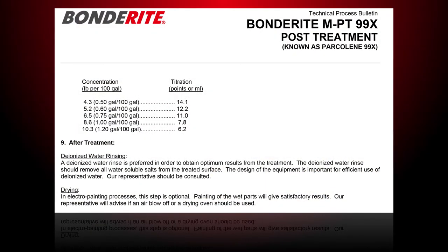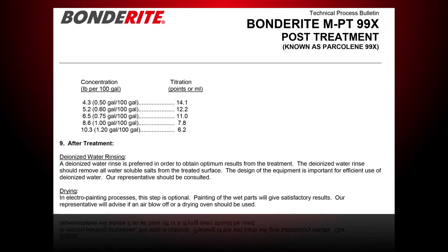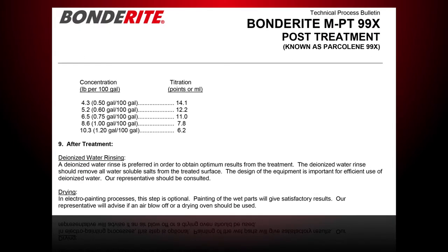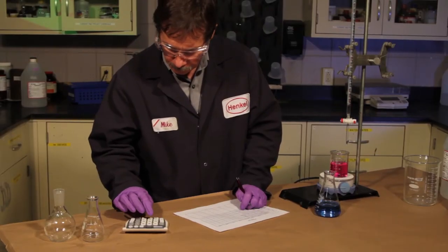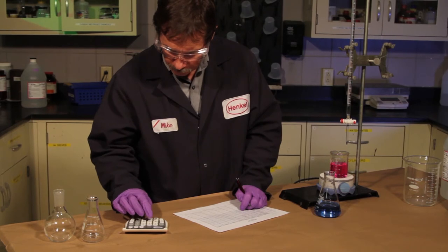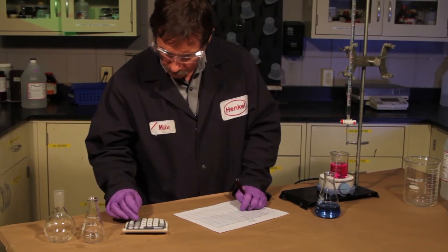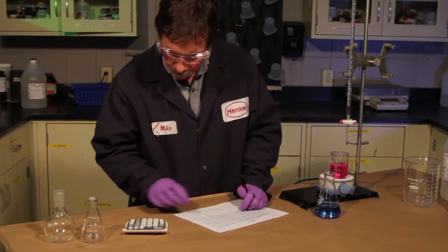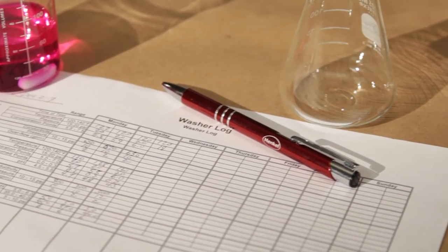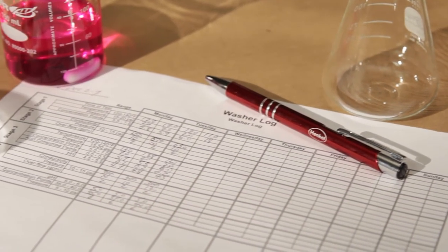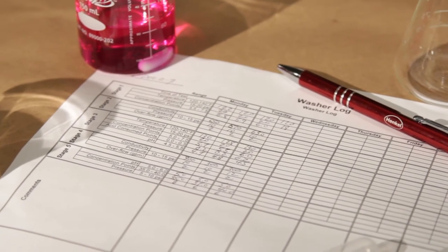The Henkel product data sheet will specify how many points or milliliters of solution to use to control your process. Now that you have measured the number of milliliters, you can compare that with your process control points and use the calculation or chart provided to determine if it is in specification or requires additions or adjustment. Record your values in a log sheet or other quality records and make note of any additions that are required.